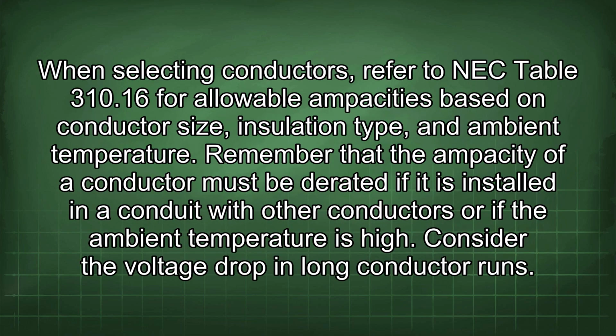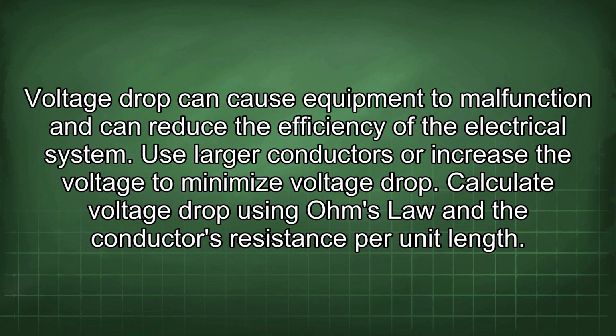When selecting conductors, refer to NEC Table 310.16 for allowable ampacities based on conductor size, insulation type, and ambient temperature. Remember that the ampacity of a conductor must be derated if it is installed in a conduit with other conductors or if the ambient temperature is high. Consider the voltage drop in long conductor runs. Voltage drop can cause equipment to malfunction and can reduce the efficiency of the electrical system. Use larger conductors or increase the voltage to minimize voltage drop. Calculate voltage drop using Ohm's law and the conductor's resistance per unit length.